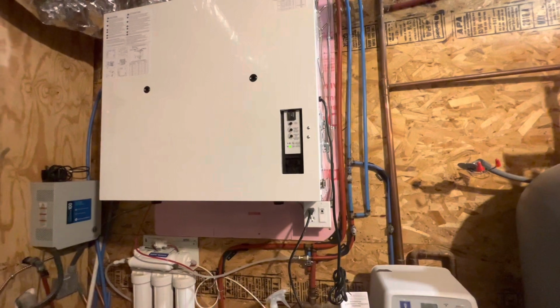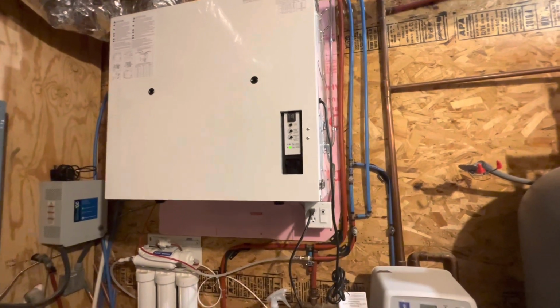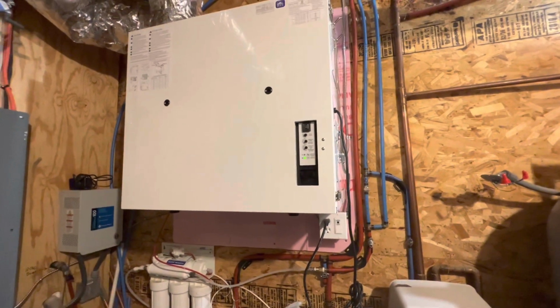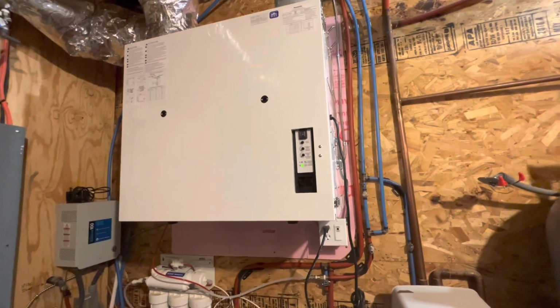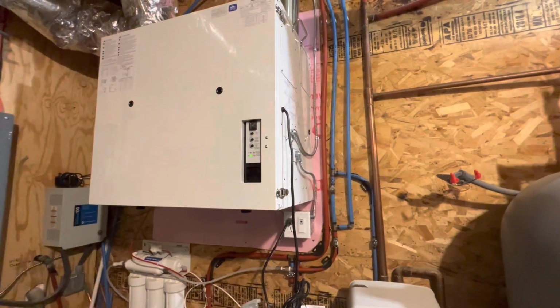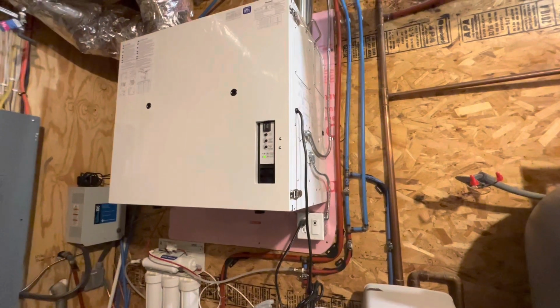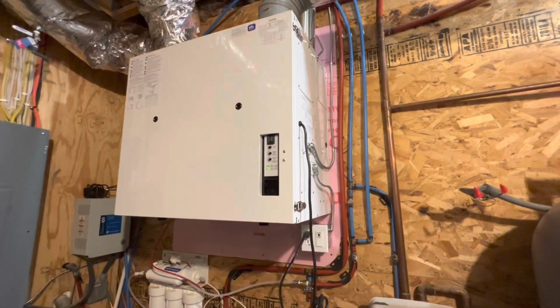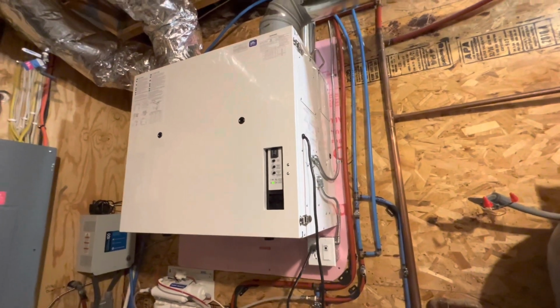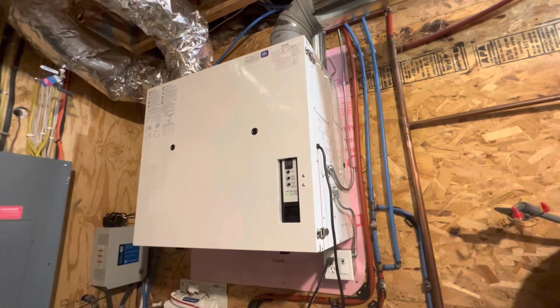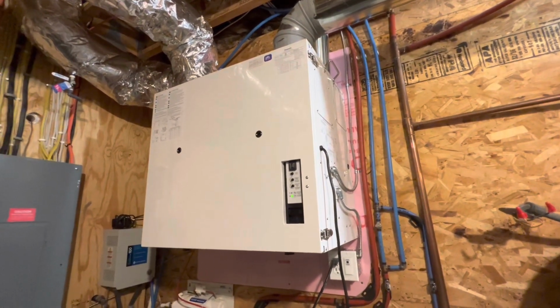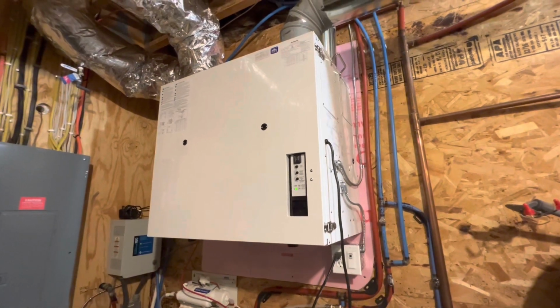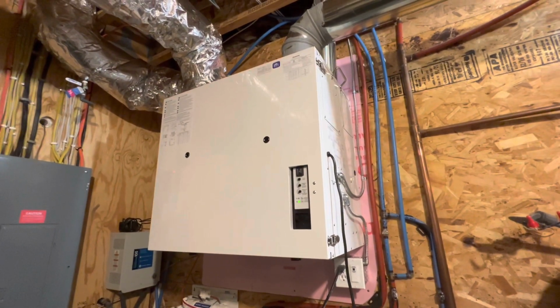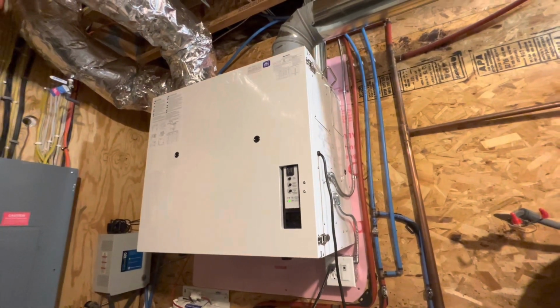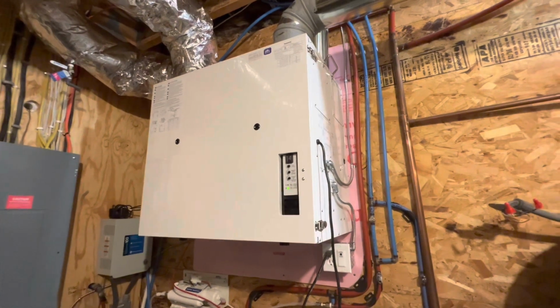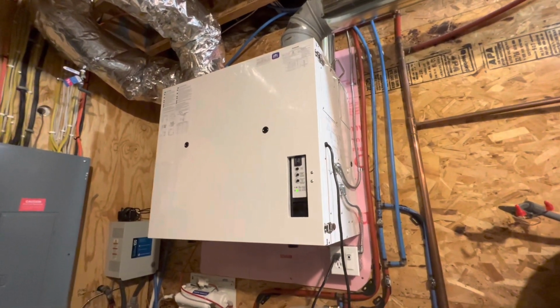So I guess back to the unit. For the install, I elected to wall mount it. The manual gives you the option to wall mount, floor mount, or hang. I did the wall mount, mounted it on a piece of rigid foam, with the thought that if it had any vibration, or just to try to dampen any noise that it might create. But this unit is so quiet, it doesn't make any noise at all. You don't know that it's running unless you stick your hand over the outside on the suction and discharge line to know that it's actually moving any air. So like I said, I did a wall mount.